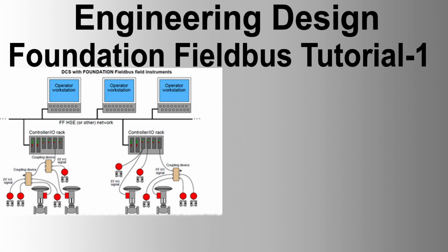Many users want to enjoy the simple installation of 2-wired transmitters. Explosive gases prevent high-performance electronics in the hazardous area of the plant. Transmission of 31.25 kbps was chosen for those applications which demand devices of very low power consumption. A field device can draw electric current from the medium to feed energy to its electronics. It is called a bus-powered device and is the Fieldbus equivalent of 2-wire installation.